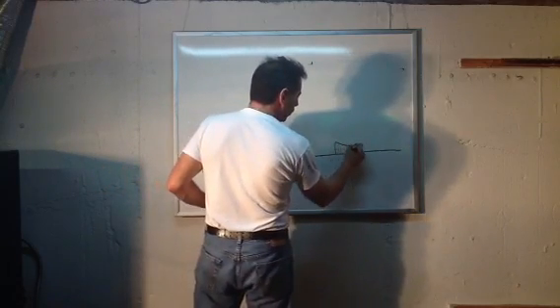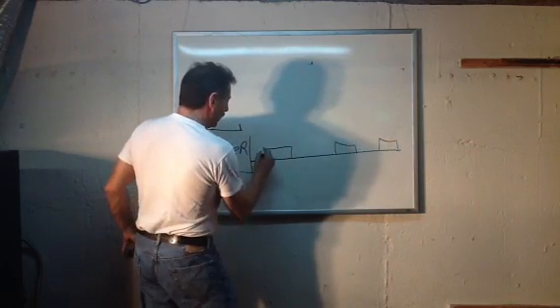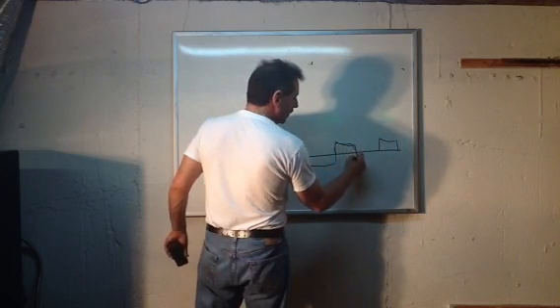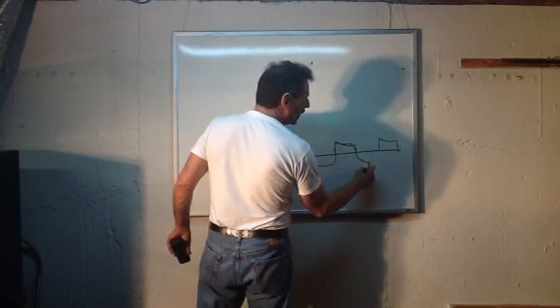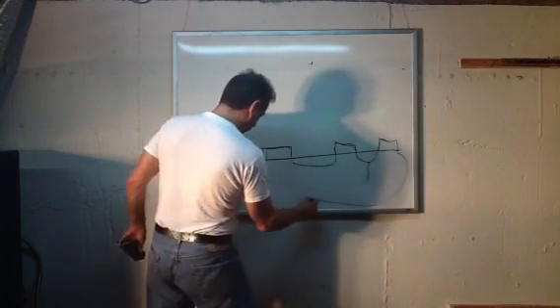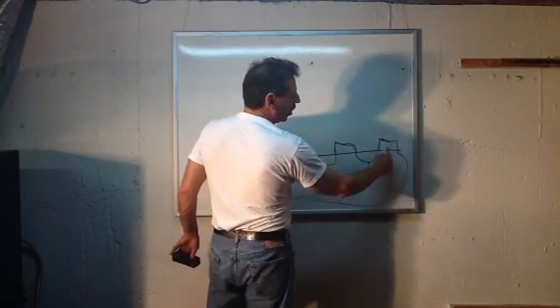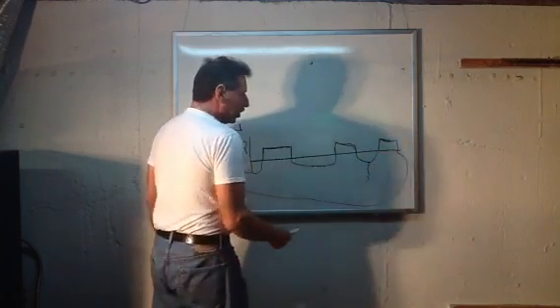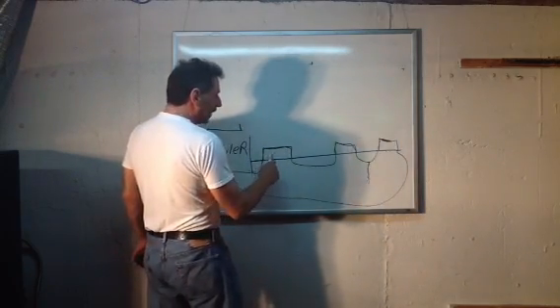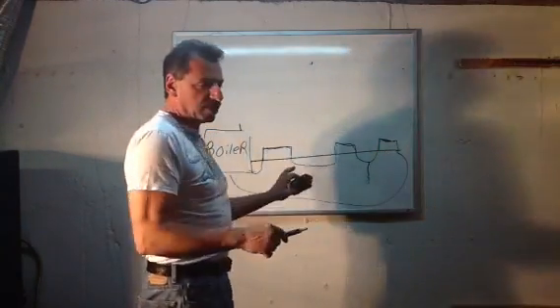Baseboard in one room, baseboard in another room, baseboard in another room. The water's traveling 180 degrees through this baseboard, down under the concrete in the sand, through this baseboard, down under the concrete in the sand. But now there's a leak back into this baseboard and then back to the boiler. So you have your water flow, but this baseboard seems to always be cool. And that's because you're losing a lot of your water in the earth, although it's traveling this way and heating these two.